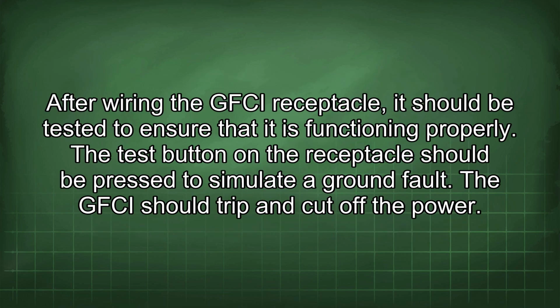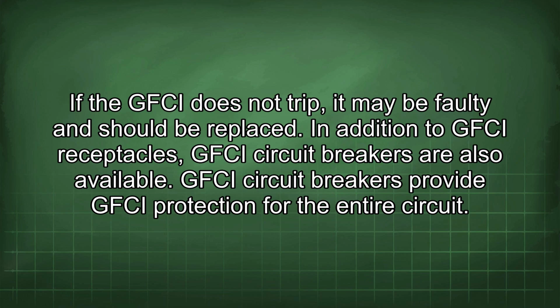After wiring the GFCI receptacle, it should be tested to ensure that it is functioning properly. The test button on the receptacle should be pressed to simulate a ground fault. The GFCI should trip and cut off the power. If the GFCI does not trip, it may be faulty and should be replaced.